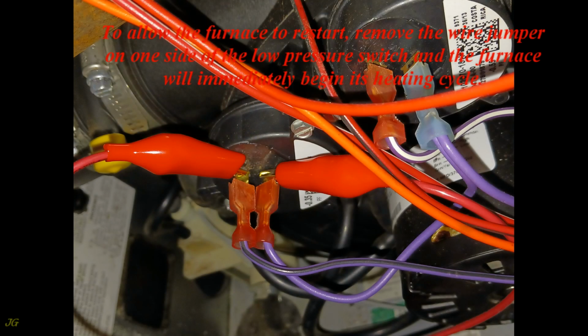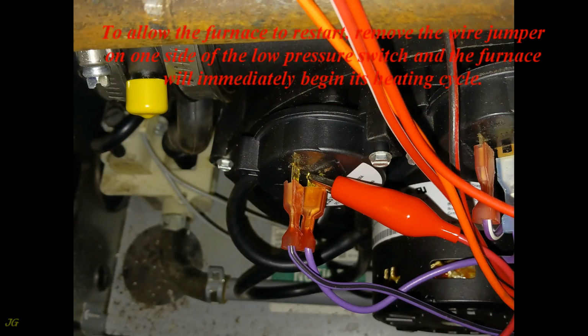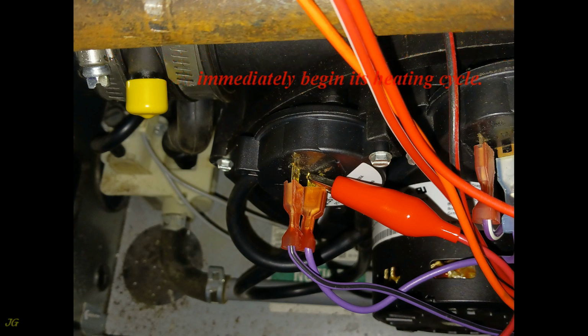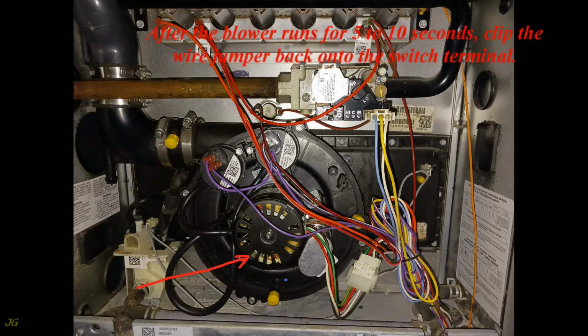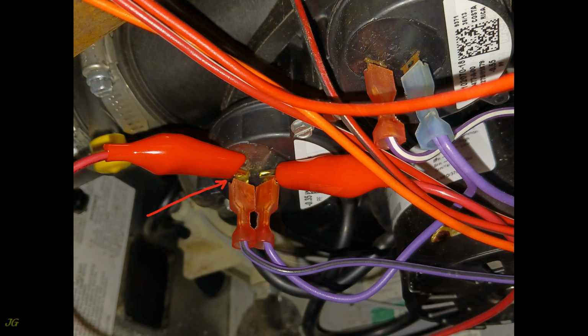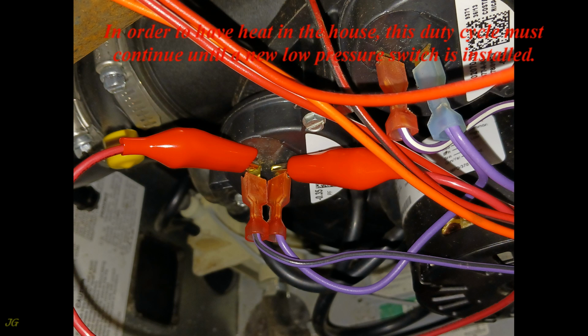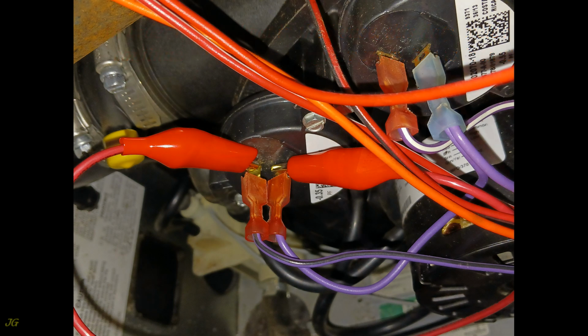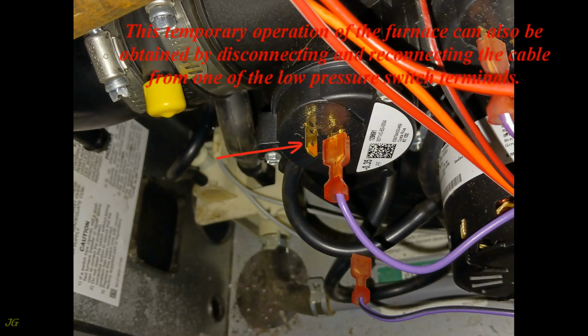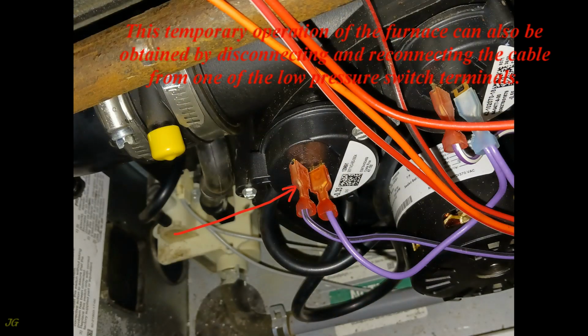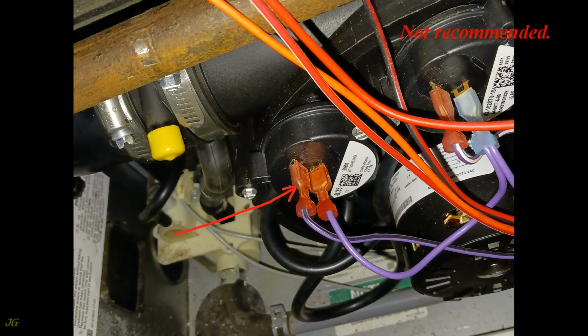When the furnace stops and the thermostat calls for heat again, the furnace will not start, it will display error code 44. To allow the furnace to restart, remove the wire jumper on one side of the low pressure switch and the furnace will immediately begin its heating cycle. After the blower runs for 5 to 10 seconds, clip the wire jumper back onto the switch terminal. In order to have heat in the house, this duty cycle must continue until a new low pressure switch is installed. This temporary operation of the furnace can also be obtained by disconnecting and reconnecting the cable from one of the low pressure switch terminals. Not recommended.